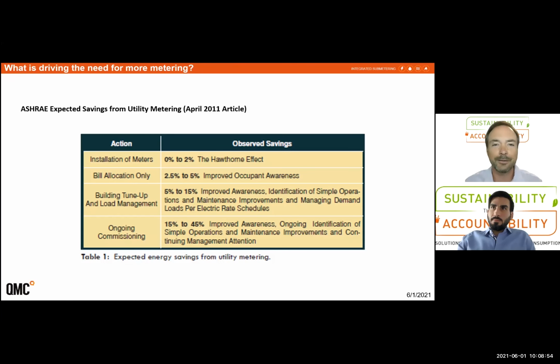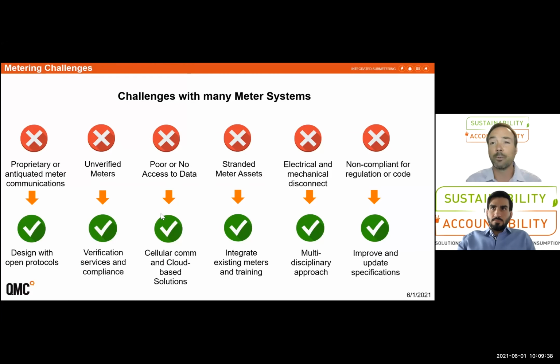And this is just a clip that I got out of an ASHRAE publication quite a few years ago, and it just shows the savings that can be achieved with a meter system in place. I actually argue that their billing allocation savings of 2.5 to 5% are a bit low. We've seen some commercial and especially residential tenants save over 30% once they're actually billed for their consumption. But the building tune-up and ongoing commissioning are obviously critical. They need meter data to see when and where utilities are being used, and if changes made to those systems are implemented, what kind of savings you get. So again, metering can really assist in the tune-up and the ongoing commissioning process. And that's probably what led ASHRAE to really implement a lot of metering in their more recent designs.